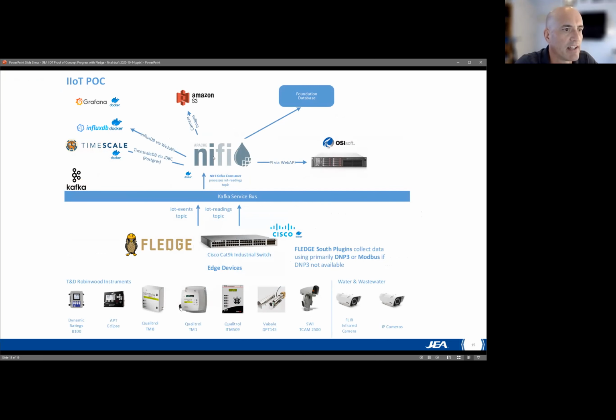We've got a suite of sensors that we're evaluating. We have things that measure temperatures and currents on the transformers, whether fans are operating, and things like that. We also have gas analyzers looking for evidence of things like arcing inside the transformer, to indicate that it's having problems and needs maintenance before we have the big explosion. We're also monitoring tap changes and things like that, so we can tell how much wear we're getting and when they need to be serviced.